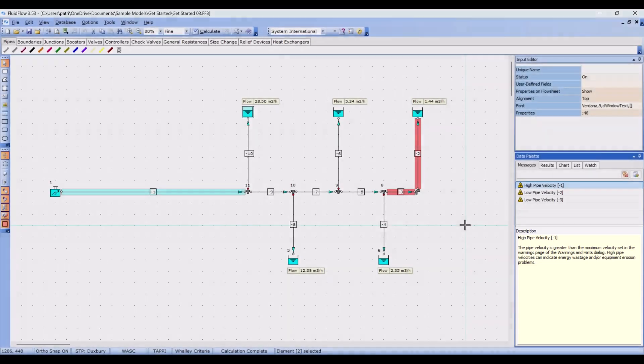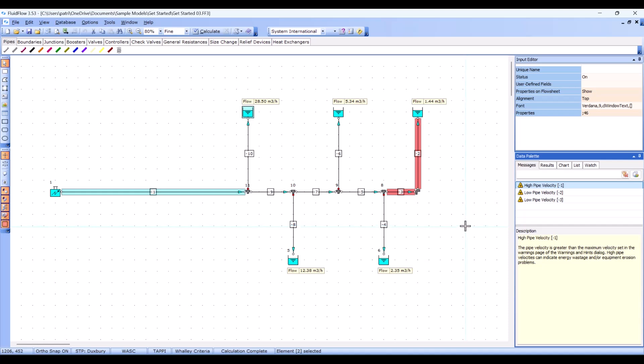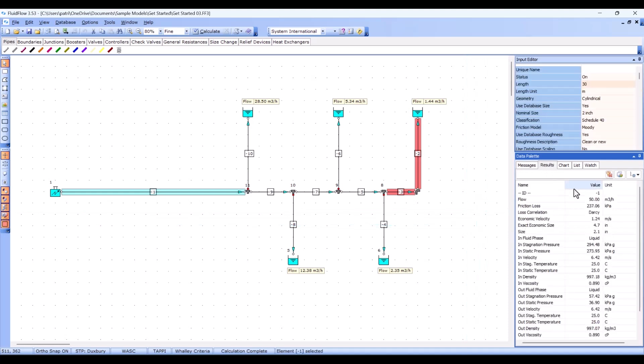In one pipe we have a high velocity, while in the other pipes we have a low velocity. If we flip to the results tab for this pipe for example, we can see a velocity of 6.42 meters per second, which is much too high for most water systems.